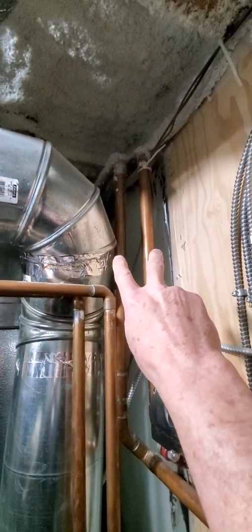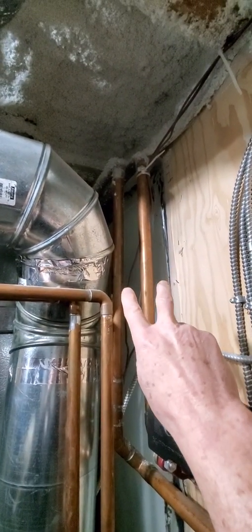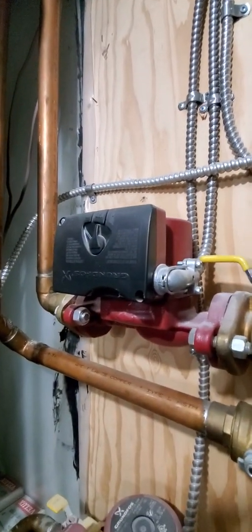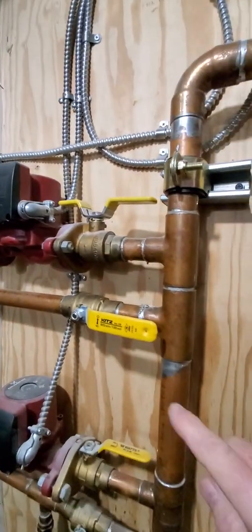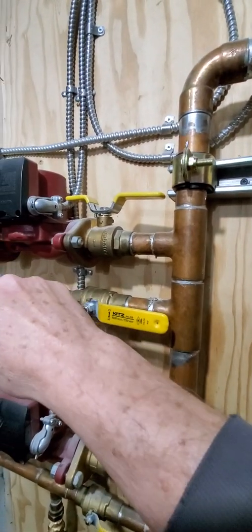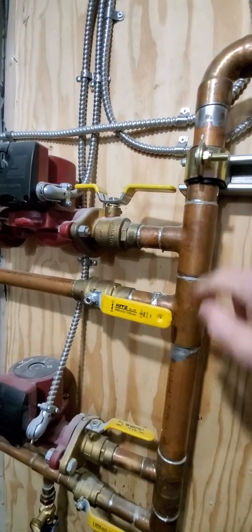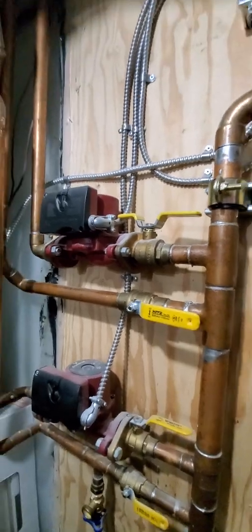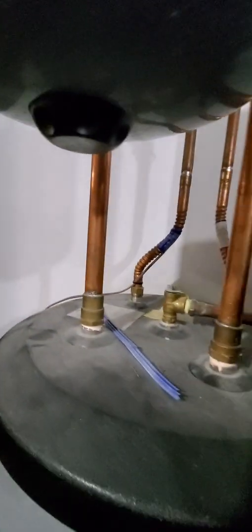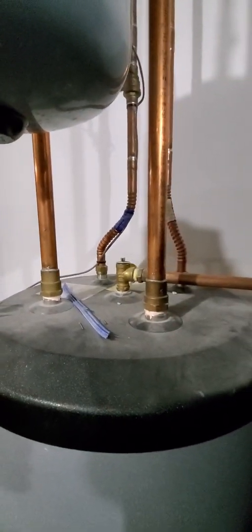These 2 lines up here are what come from the other system in the other utility room I was showing you. Also have to have a little pump on them. But basically it's just circulating to that other room and back here. So it's either going to drop off or pick up heat as needed. And there's the in-floor heating, which it will also heat all that. And then of course we have our water heating.